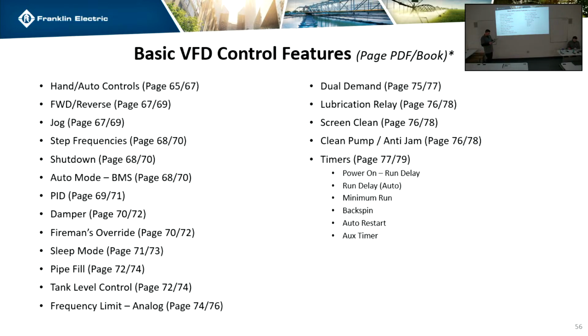And then the new feature for this drive that we haven't had before is that in Fireman's override, you can have it look at the PID. The way we had it before, Fireman's override was full speed. You just go full speed basically until the drive malfunctions. Now you can have it look for pressure. So if you are pressurizing a stairwell or something, it's not just going to max the pressure out and make it so you can't open any doors. And then the only other option for Fireman's override that's settable, oh no, we got more, okay.